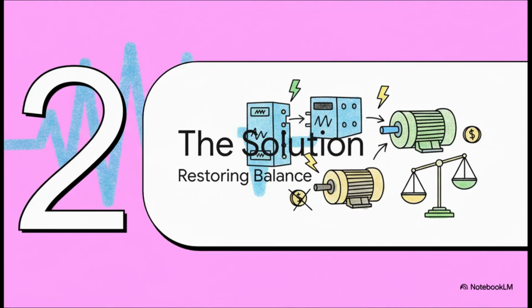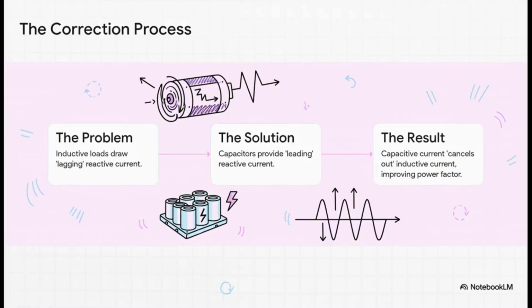Okay, so we've laid out the problem, but the good news is there's a really elegant and effective solution. It's time to bring in the hero of our story, the capacitor. So here's how it works, broken down really simply. Our motors, those inductive loads, they create a lagging reactive current. Now capacitors do the exact opposite. They provide what's called a leading reactive current. So when you add capacitors to the system, their leading current essentially cancels out the lagging current from the motors. The end result? A much, much healthier power factor, getting you way closer to that ideal target of 1.0.